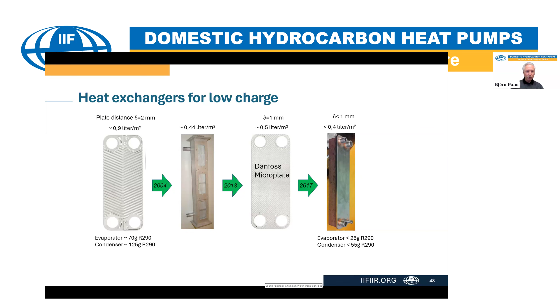We made some prototypes already 15 years ago, which had 0.4 liters per square meter of heat exchange surface based on aluminum microchannel tubes. Now Danfoss has microplate heat exchangers which can give us about 0.5 liters per square meter, and the pressing depth is 1 millimeter in that case. And we also did some prototype heat exchangers with a pressing depth of less than 1 millimeter, and in that case we could get less than 0.4 liters of volume inside the heat exchanger per square meter of heat exchange surface. So there is a lot to do also with heat exchangers to decrease the charge.